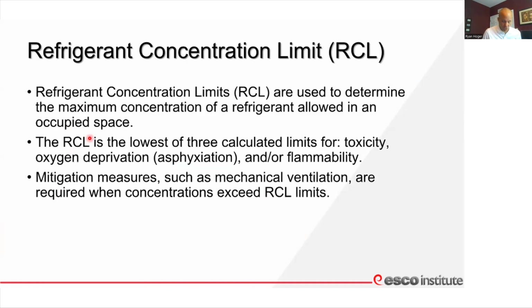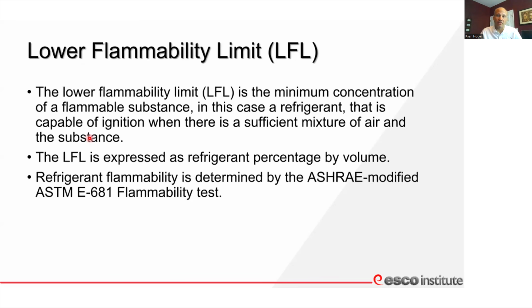All right. There are two terms from the ASHRAE standard that we're going to pay attention to. There's a bunch of different terms, obviously, but one is refrigerant concentration limit. The other one is lower flammability limit. Refrigerant concentration limit is a number that ASHRAE assigns to each and every refrigerant to express how risky that refrigerant is. How flammable is it? Oxygen deprivation, toxicity, all those scary things wrapped up into one number, if you will. And every refrigerant has that, including 410A. We've always had that kind of stuff. We just haven't had to take any action on it really, for the most part. Sometimes on VRF we did. Then there's lower flammability limit, which is something we definitely ignored on our other refrigerants because it was zero, but now we have to deal with that.